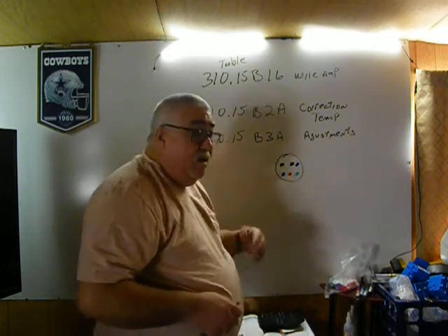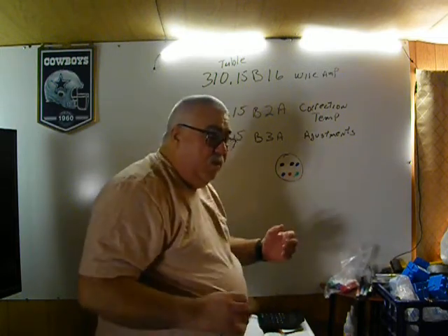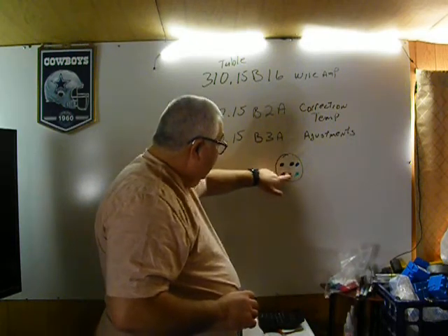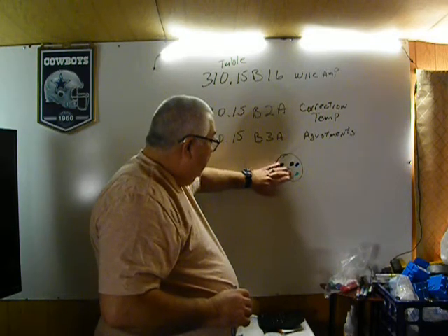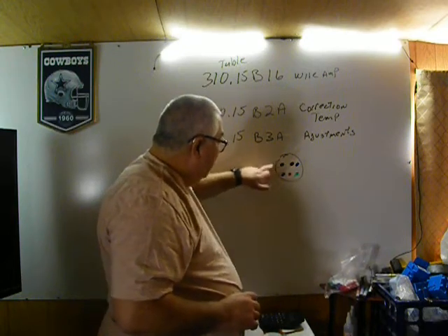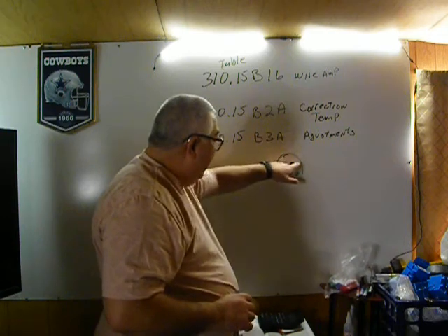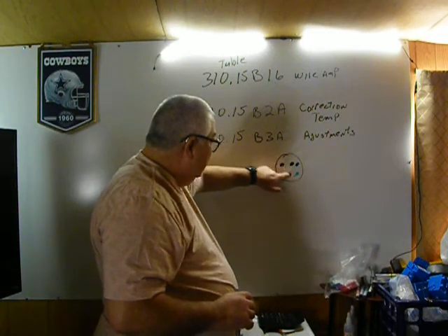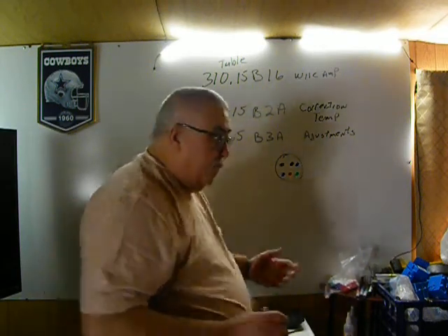Okay, here, when is it a current carrying conductor? When is it not? If it was in a residential, we really wouldn't care, but we should look into this. These black and the red go with the neutral. This neutral does not count. Because we're only taking one phase out of our hots, we have to count the neutral. So in this one we have 3 current carrying conductors: a black, white, and a red. We don't have to count this one because the ampacities of this one will cancel out the ampacities of this one, so the neutral shouldn't be carrying any current.